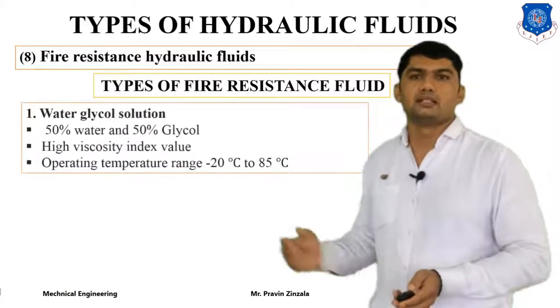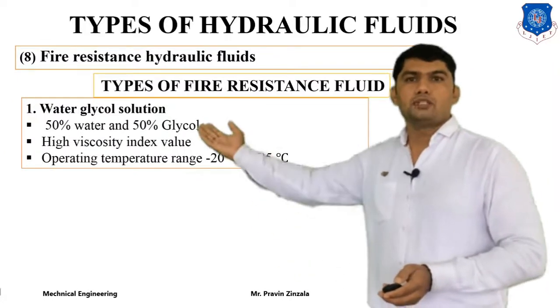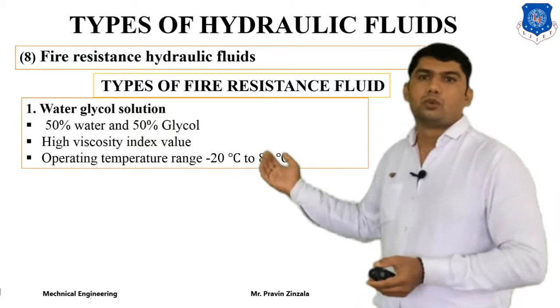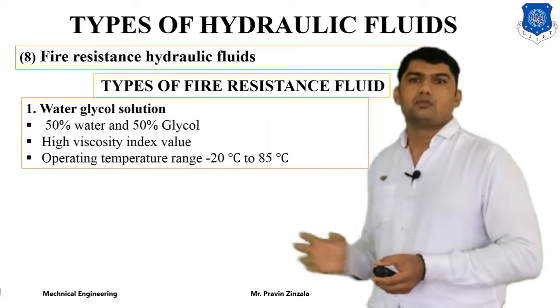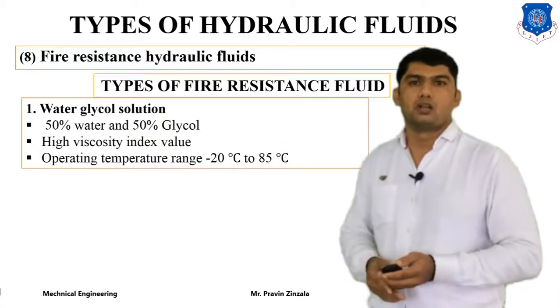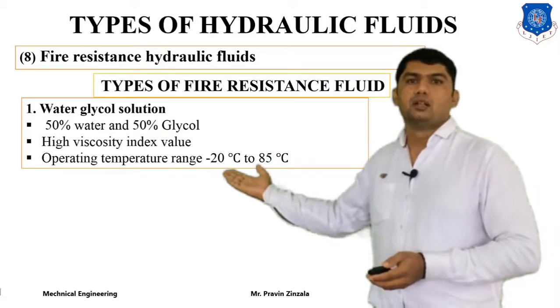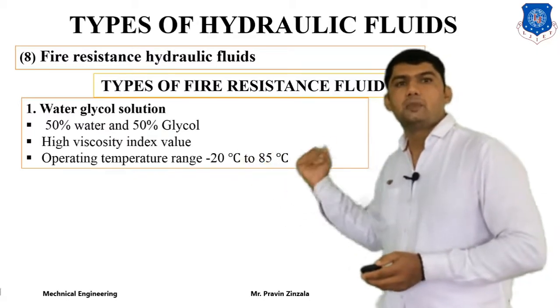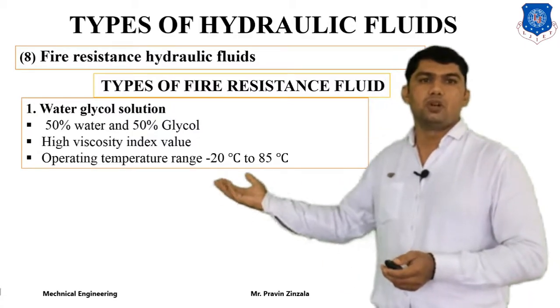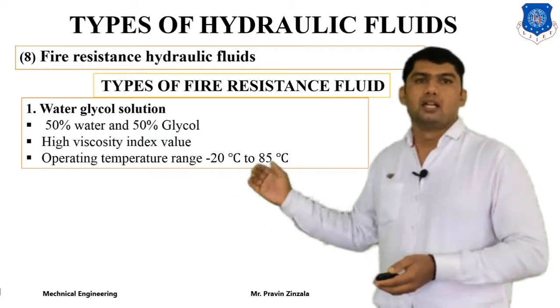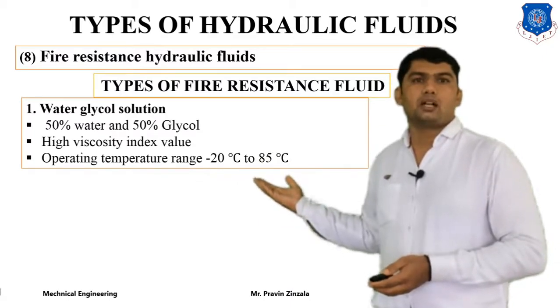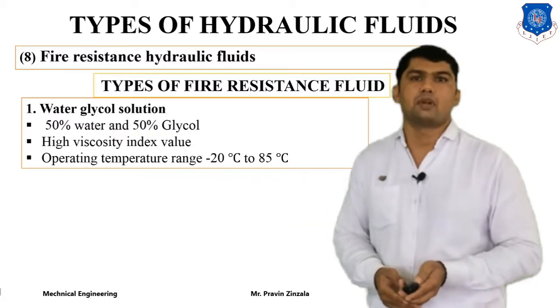The first fire resistance fluid is water glycol solution — 50% water and 50% glycol, with a proportional ratio of 1:1. It has a high viscosity index compared to water and vegetable oil, and its operating temperature range is minus 20 degrees to 85 degrees centigrade. So we can easily operate at lower temperatures, for example in foreign countries where temperature is below zero, and also up to 85 degrees centigrade.